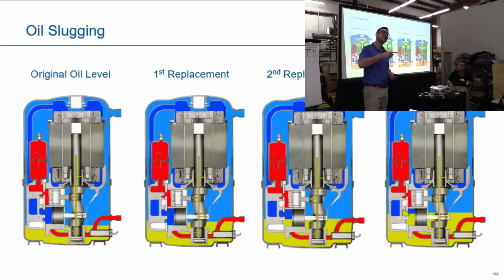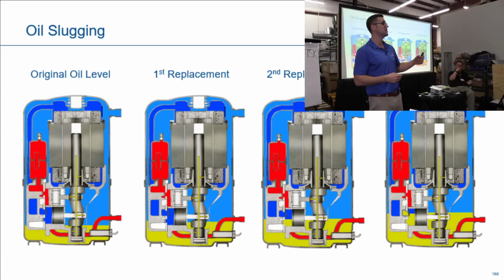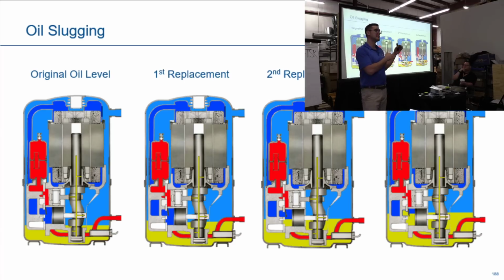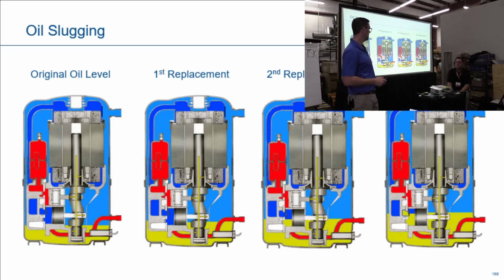So there's some things that you need to look for though, because oil is one of the hardest things for me to diagnose. So if you go up and you see a massive leak and there's oil everywhere and then you check it and you're down 10 ounces of oil, well maybe it most likely leaked from that, it left the system from that leak, so you wouldn't pour any out. But if you have no leaks in the system, you pull out all the gas and then there's no oil in there, most likely that oil's in the system. You probably should drain a few ounces out of that compressor. That's why you've seen our recharge is lower than our OEM charge of oil. So if it's in the system, and you're down 10 or 20 ounces, then maybe you have to pour some out. Always measure oil if you don't have a sight glass.